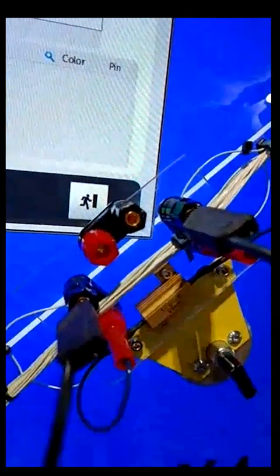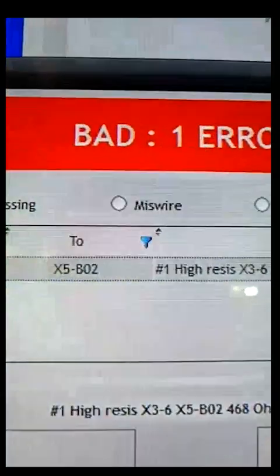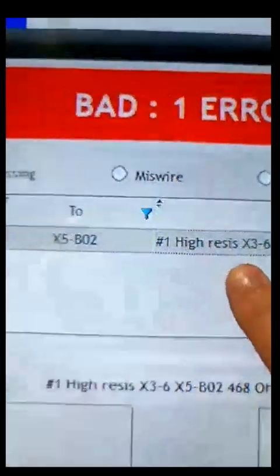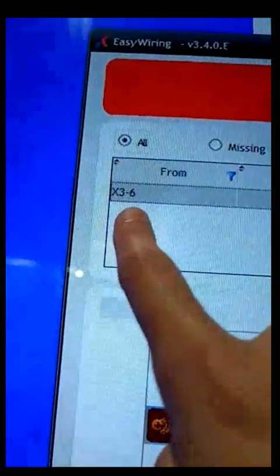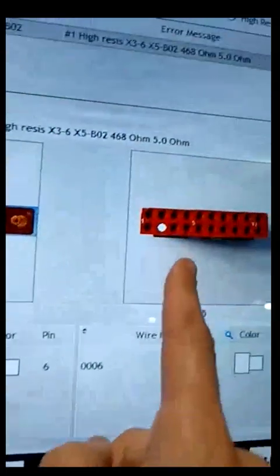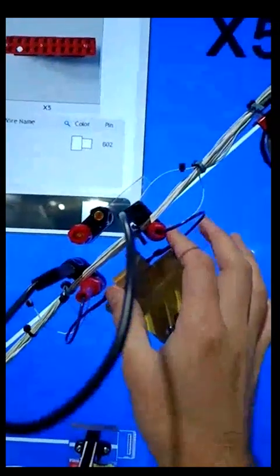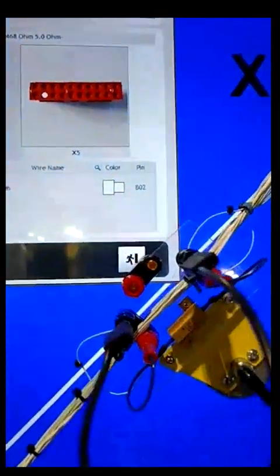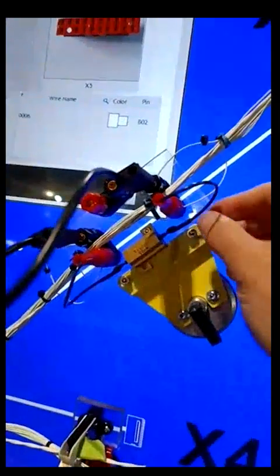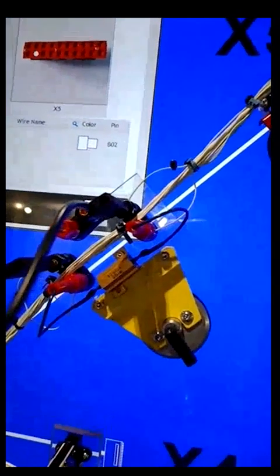So whenever I run the test here, it's bad, one error, and it's telling me there is high resistance in the cable going from X36 to X5B02. I have all the information, so I need to go check these contacts to make sure that wire is good in the harness, because there is a connection, but the resistance is too high. It's not a normal wire, there's a problem with it.